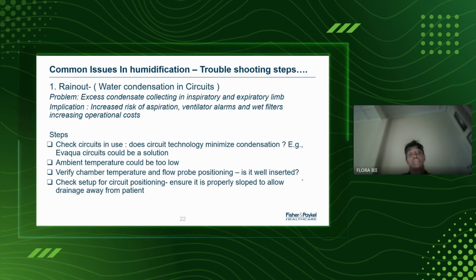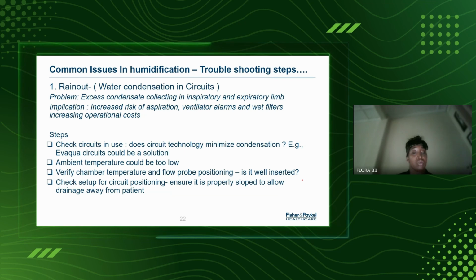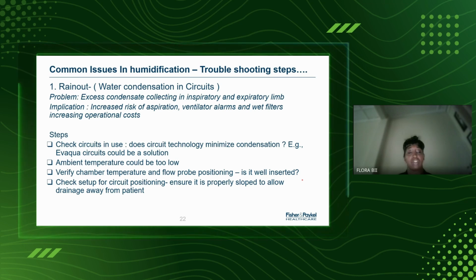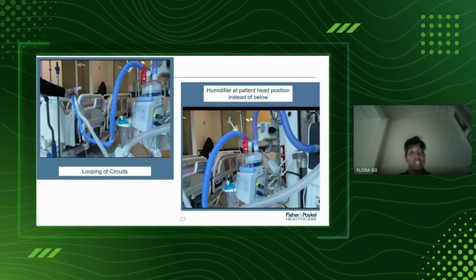And also you'd need to check the ambient temperature. Could it be too low? In this scenario, you'd find that with ambient temperatures being too low, you'd have some water forming in the circuits, for example. You'd also need to check the chamber positioning in terms of the temperature and flow probes. Is it well inserted? These are some of the issues that you would face.